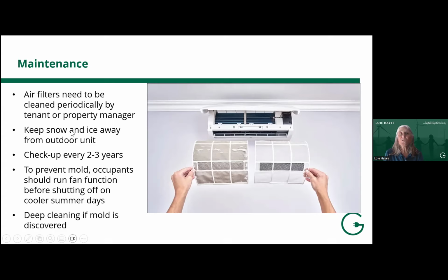The other big important thing is the outside unit needs to have snow cleared away from it. If we're getting a snowpocalypse year, you need to get out there with a shovel and make sure snow isn't building up so ice doesn't encase the unit and restrict the airflow. You can also do a checkup every 2 to 3 years with a professional.